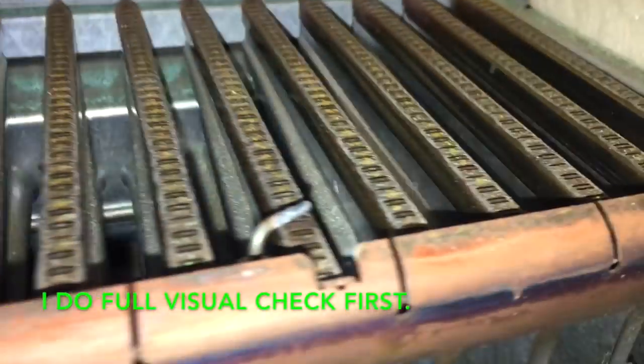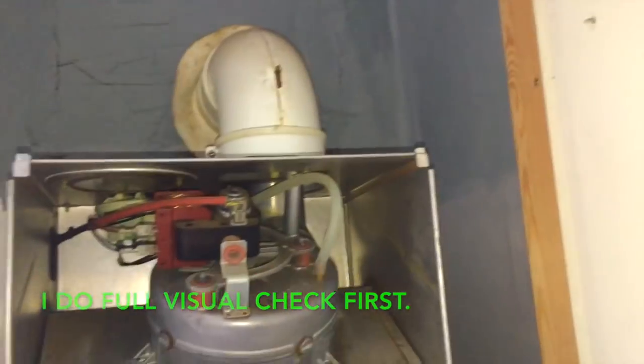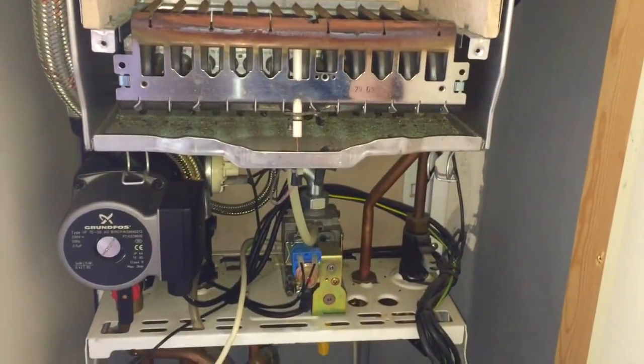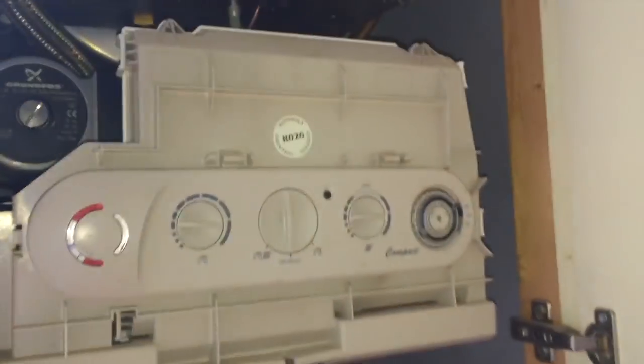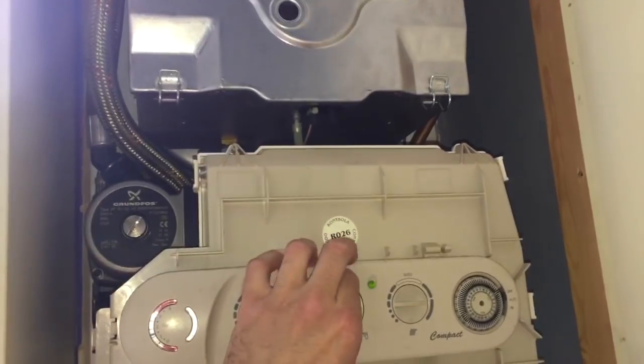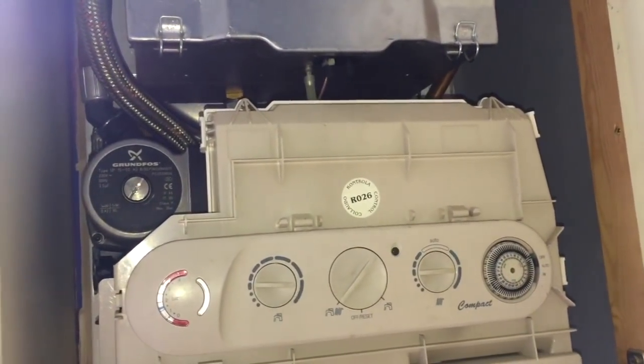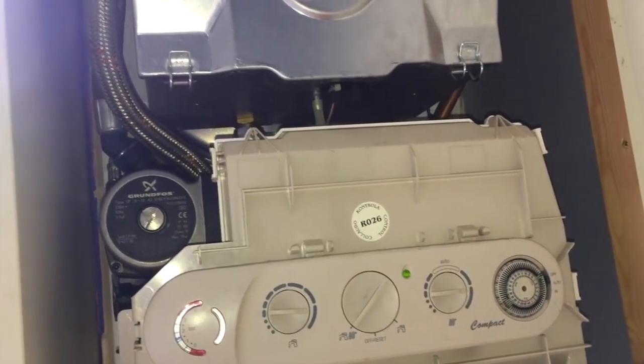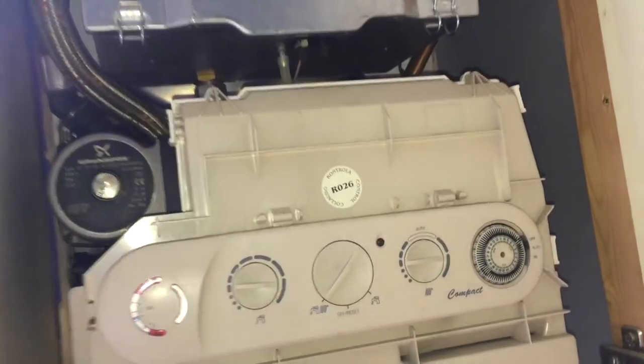Okay, so this electrode's a bit dirty, heat exchanger's not bad, a little bit crusty but nothing major there. So I'll clean that electrode up, I'll give the burner a little wipe over, put it back together and start testing. Fans running. Then ignition. Okay.